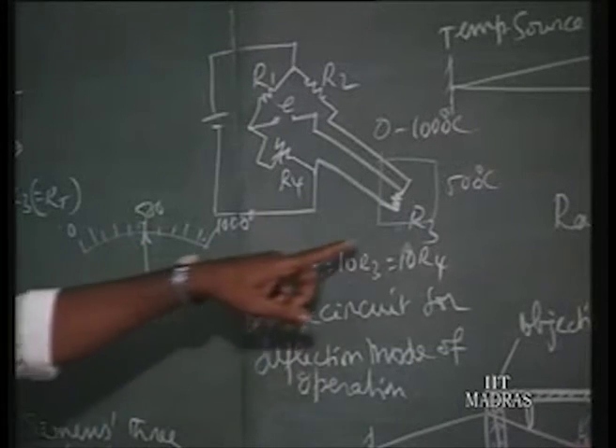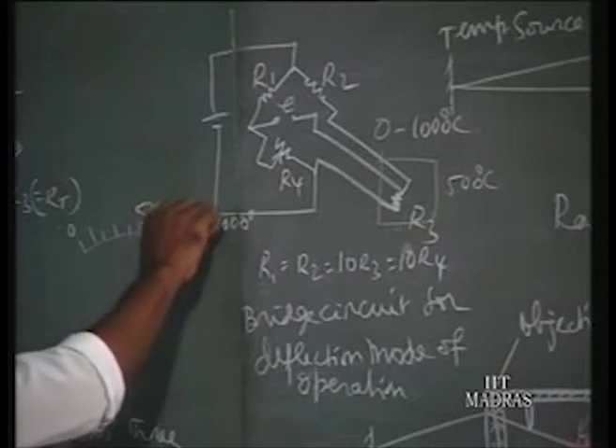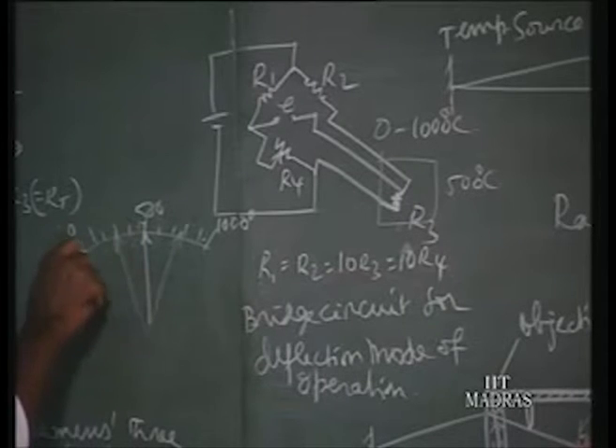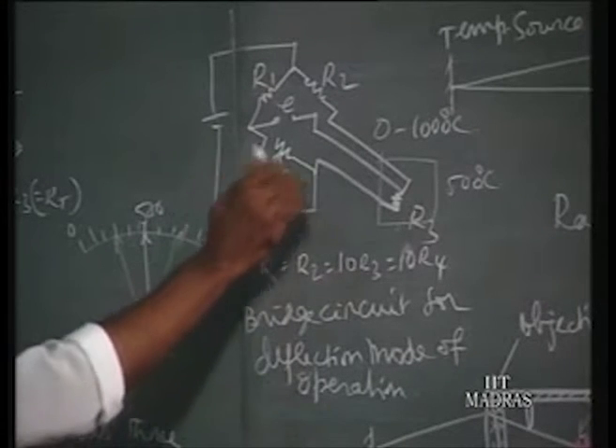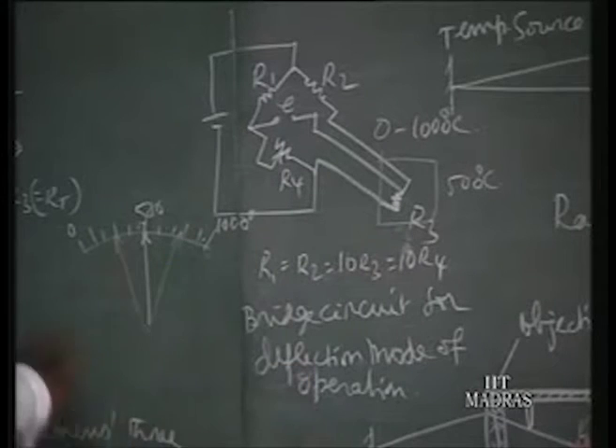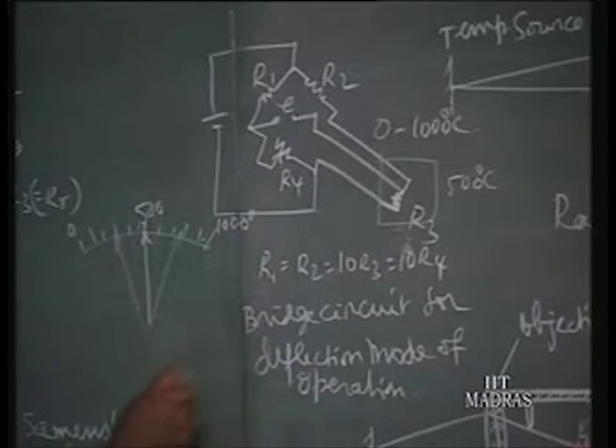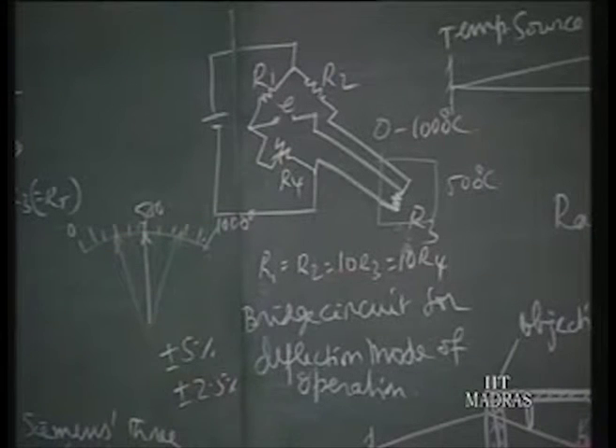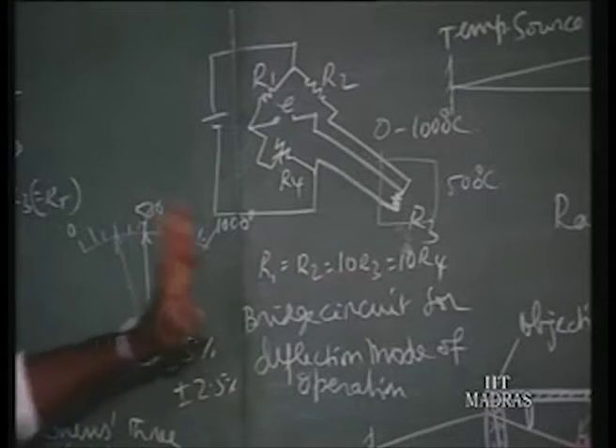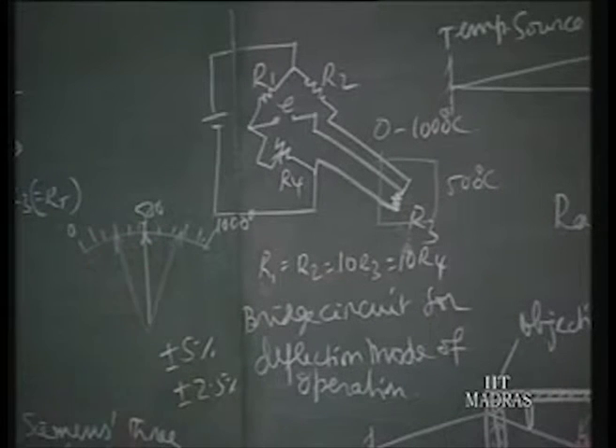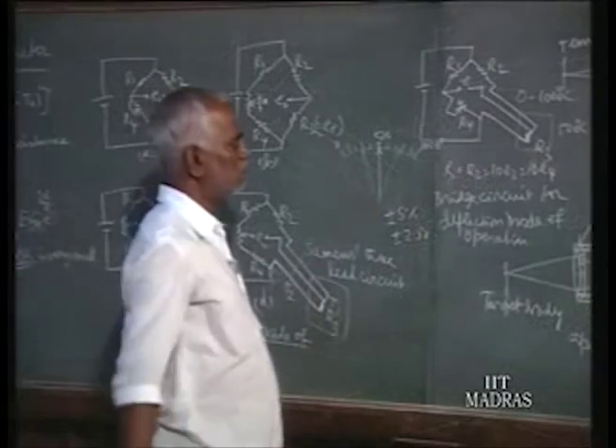At 500 degrees the voltage read is 0. Any increase in temperature moves the pointer in one direction and decrease in temperature moves it the other direction. So the non-linearity is between 0 and 500, and 500 and 1000, reducing total non-linearity to nearly half. Previously, for 0 to 1000 degrees, it was plus or minus 5 percent non-linearity. By this design, we can reduce it to 2.5 percent — by having zero voltage for the middle of the range, we reduce total non-linearity to half for the full range.